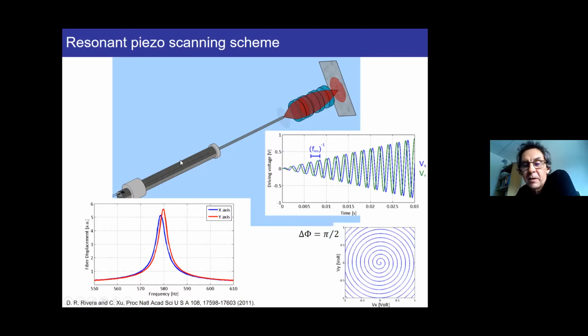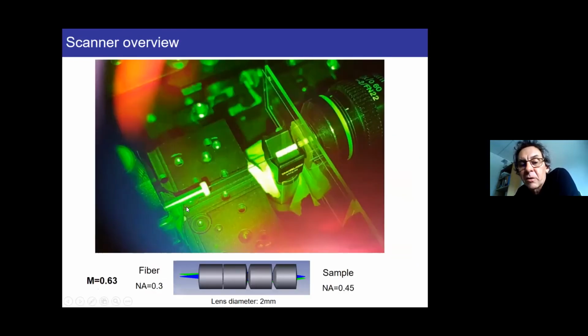So altogether, it's a small scanner, and that's a view of the scanner here when it's completely dismantled. You see here you have the piezo tube. This is the fiber optics, and as you understood, when you shake this one at the resonant frequency, then you shake the end of the fiber that makes the spiral, and this is the micro lens that images the end of the fiber down to the sample. This objective lens was there for calibration purposes, but the full system is only this kind of tube. And this is the design of the distal objective lens, which in this version has a 0.3 numerical aperture on the fiber side, and 0.45 on the sample side. Now our last version has 0.7 numerical aperture. So hopefully we can collect enough signal.